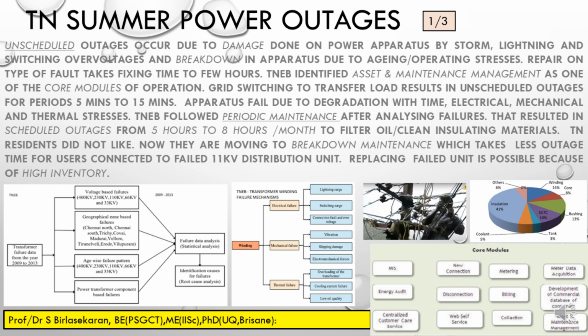TNEB identified asset and maintenance management as one of the core modules of its operation. Grid switching to transfer load results in unscheduled outages for periods of 5 minutes to about 15 minutes. Apparatus fail due to degradation with time, electrical, mechanical and thermal stresses. You can see at the bottom some 2 or 3 slides on that failure mechanisms.